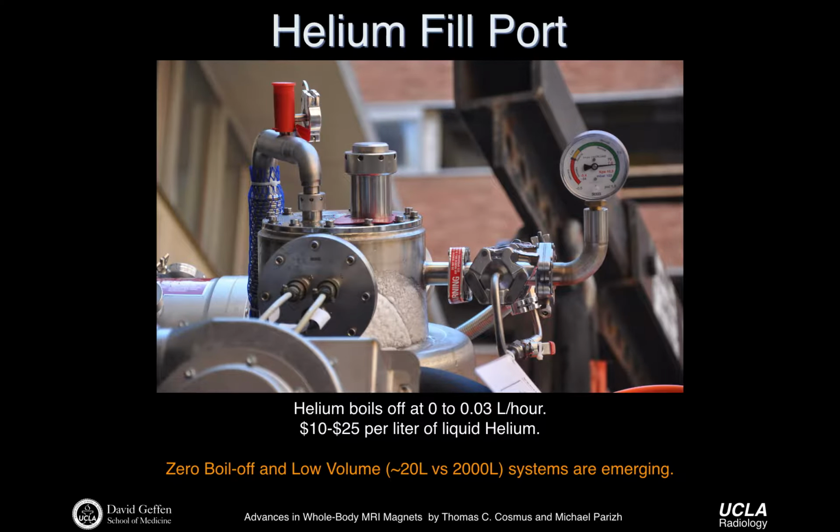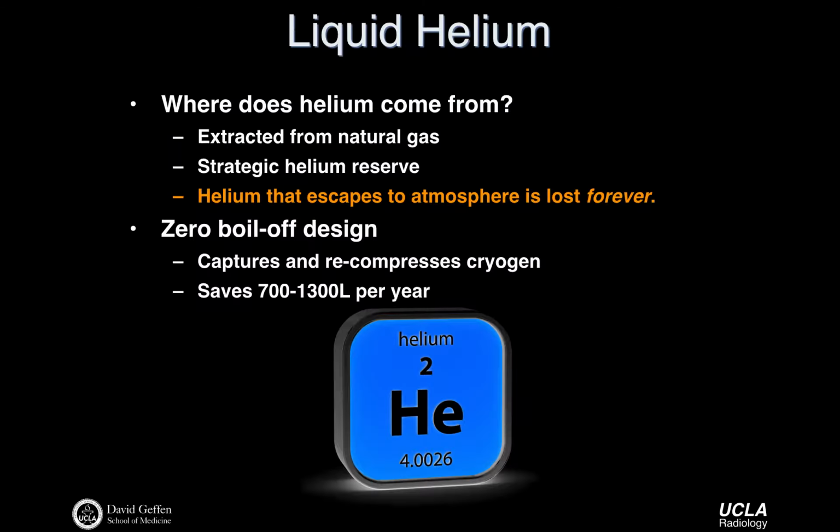There's a helium fill port. I won't dwell on this too much, but helium is pretty expensive. It boils off, depending on the system. There are so-called zero boil-off systems now. Older systems boil it off at some rate per hour. But helium is pretty expensive. It's about $10 or $25 per liter. Older systems would use about 2,000 liters of liquid helium, so you'd have a pretty serious investment in helium, or at least at the time, that was the design of those systems. Again, that's changed quite a bit in the last few years.